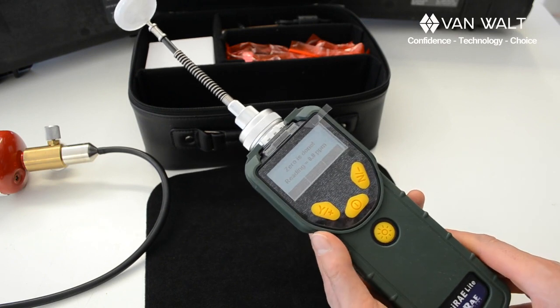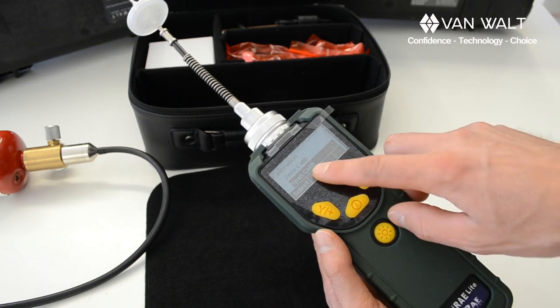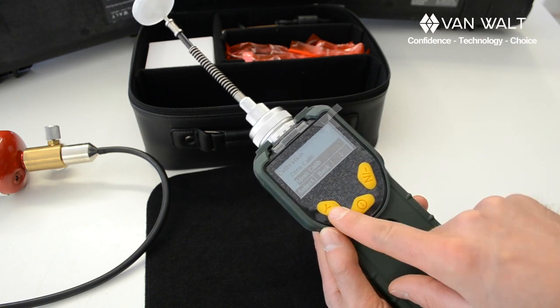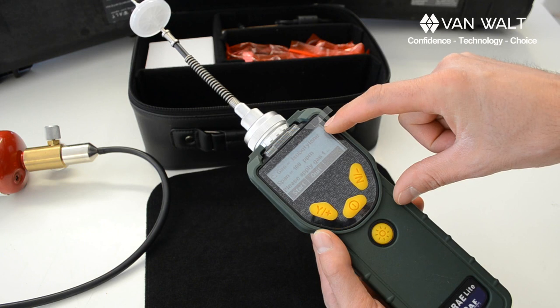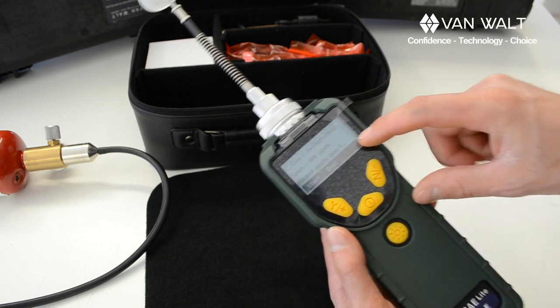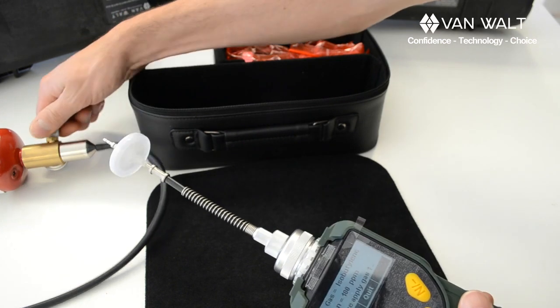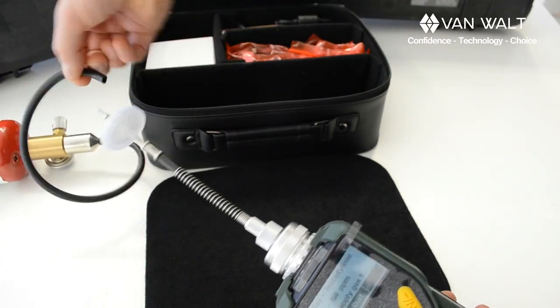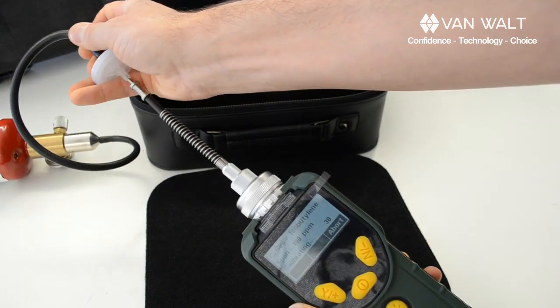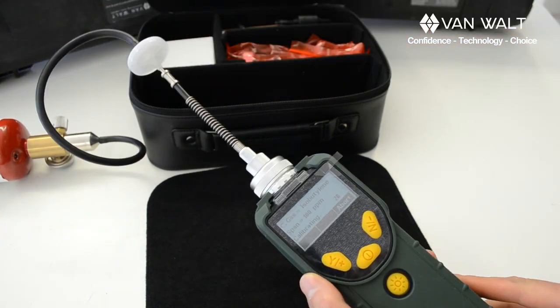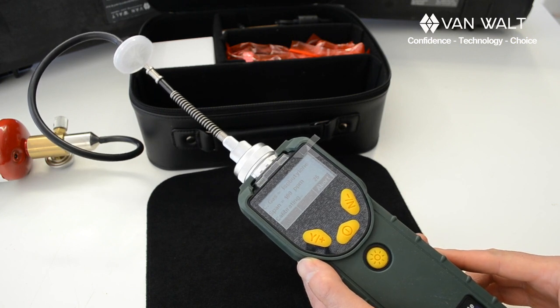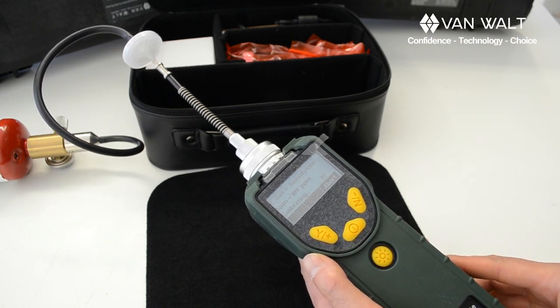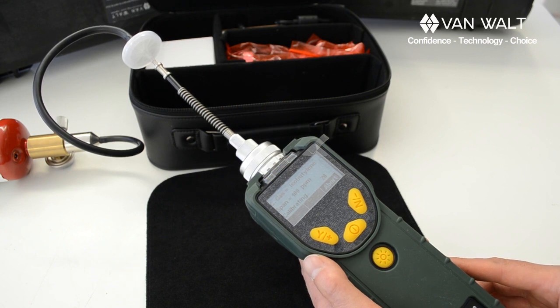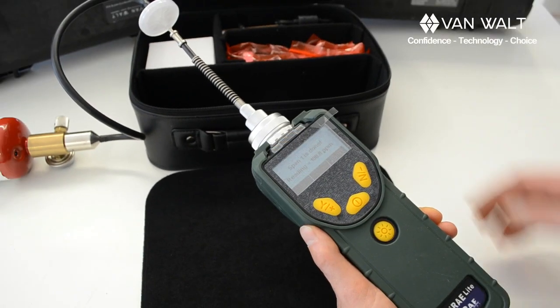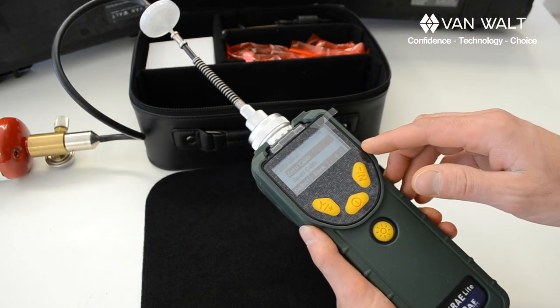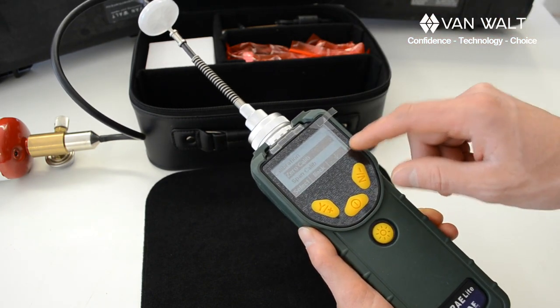Zero is done, and the reading is 0.0 ppm, and now it's asking for our span, so select isobutylene, 100 parts per million, please apply the gas. So that's what we'll do. We'll turn the gas back on and connect it, and it's recognised that the gas is connected, and it's immediately gone to its calibration and again counting down from 30. Now it says span 1 is done and it's reading 100 ppm. It's just gone back to the cal screen.